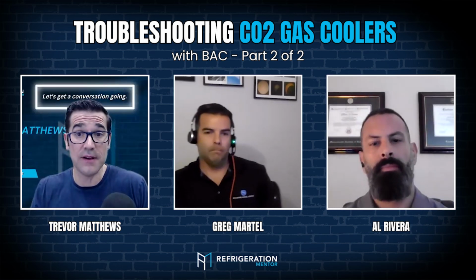Okay. So when they get up there, let's talk about this call. So this has happened. We get the digital input saying, "Hey, we need that pump running, but that current sensor is not sensing any current through that wire." So I'm assuming one thing, that current sensor could be dead. So you go up and actually check it with a meter. What should they see when they're checking the current sensor?